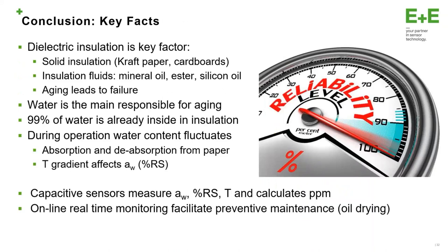So at the end, the last slide, the conclusion of today's discussion. The dielectric insulation plays a key factor inside the transformer — we have solid insulation and insulation fluids which are exposed to aging because of the working of the transformer. The aging leads to failure. Water is the main responsible factor of aging, and 99% of the water is already in the insulation layers. During operation, the water content is changing because of the temperature variation, temperature gradients, and the absorption of water molecules from the paper. So thanks to the capacitive sensor, we can measure the oil condition and the water presence inside the oil in real time, and we can facilitate preventive maintenance for the transformers.